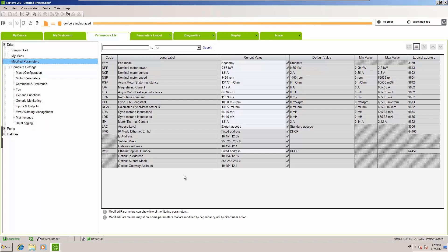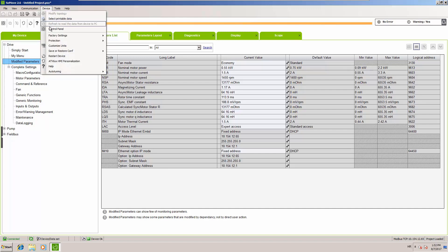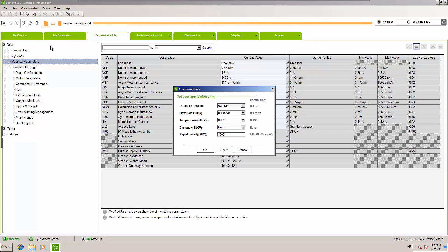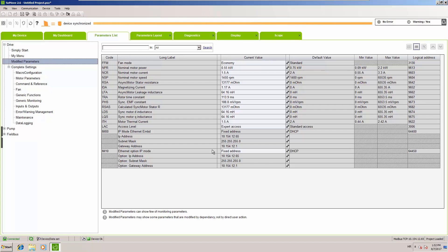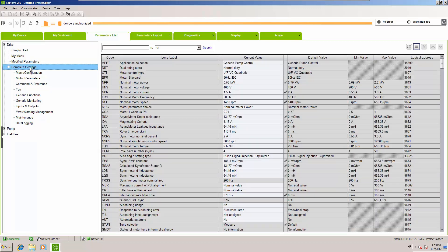Once that is done you can go to the application and start working on application parameters. In our particular example it is mainly PID and everything that surrounds it. Before we begin, because we will use pressure and flow, we need to set up user units: for pressure we use bars with 0.01 bar resolution, and for flow we use 0.1 cubic meters per hour.